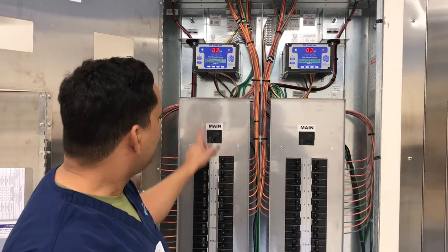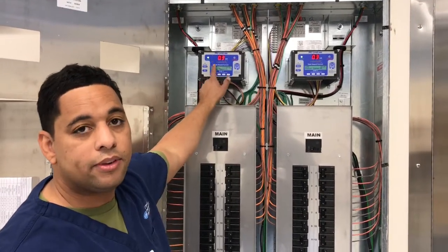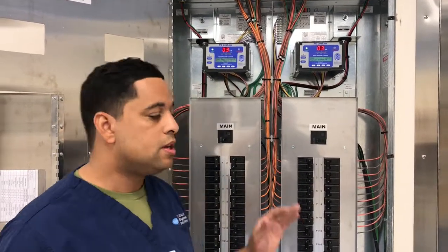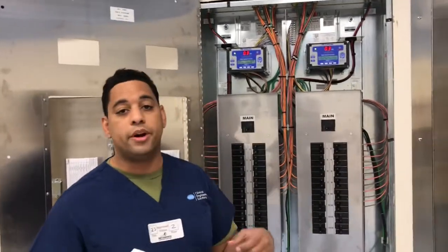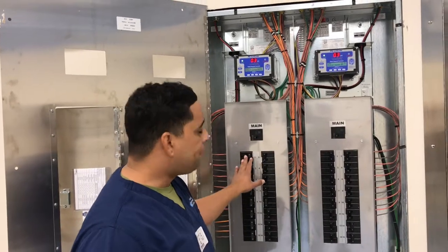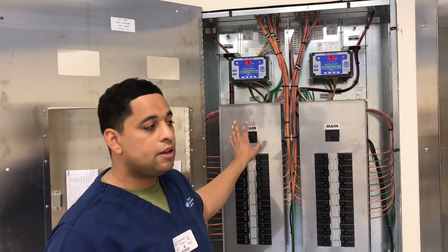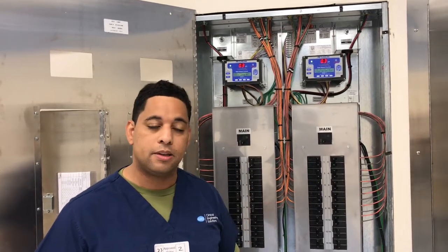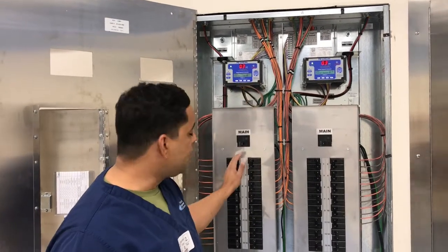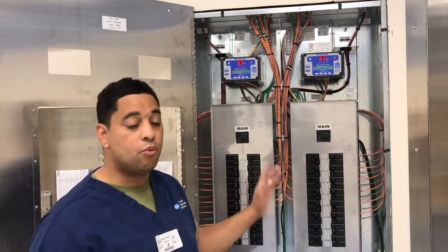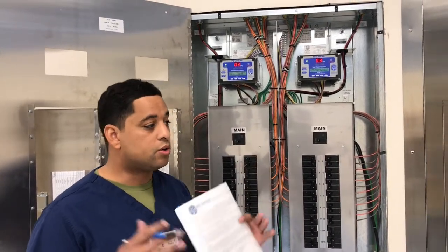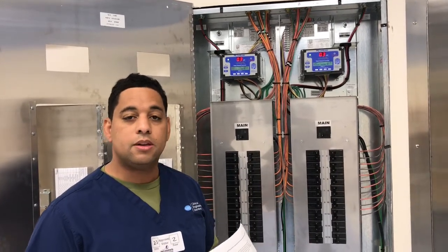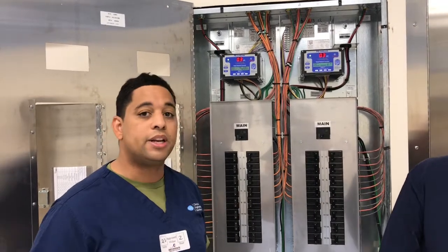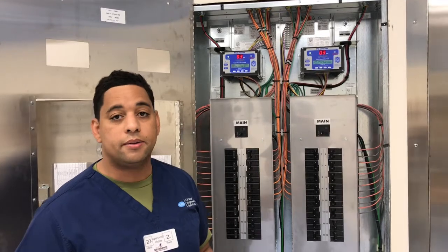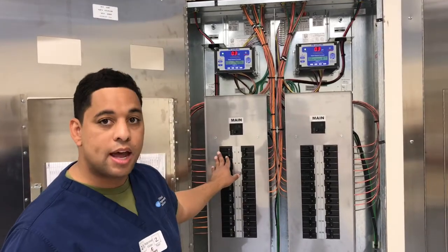Now, why does this have to alarm? And why is this necessary? Very important reason. Unlike a breaker box in your home or in your office or in other areas of the hospital, the power remains on at all times. If there is a device that has an electrical problem, and this goes into alarm, it's not going to trip the breaker. The breakers will not shut off for one very critical reason. They do not want critical medical devices to lose power. For example, an anesthesia machine, a ventilator, defibrillator, and we could go on and on. You don't want to lose power to a device that is providing life support to a patient. So the power remains on at all times.